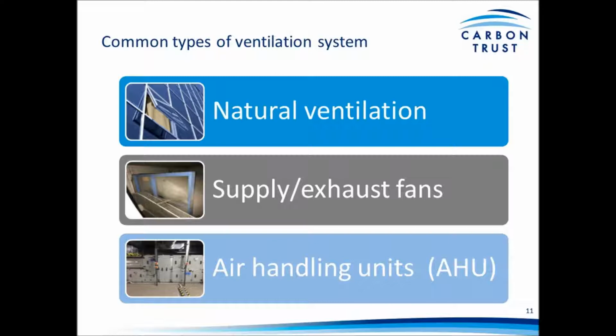One of the more basic arrangements for mechanical ventilation is to have individual direct supply fans to push air into the building, with exhaust or extract fans to take it out. That's more simplified mechanical ventilation systems. In larger buildings, you may see a packaged air handling unit, which can both supply and extract air, but will also often contain coils to heat or cool the airflow before it enters the occupied space.